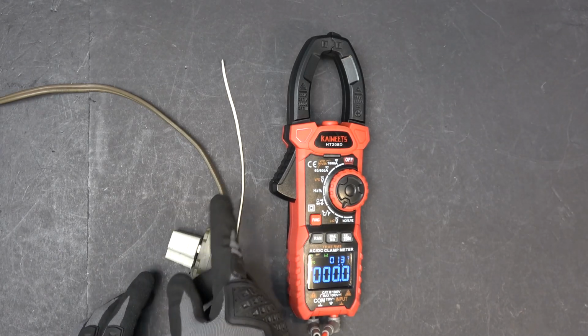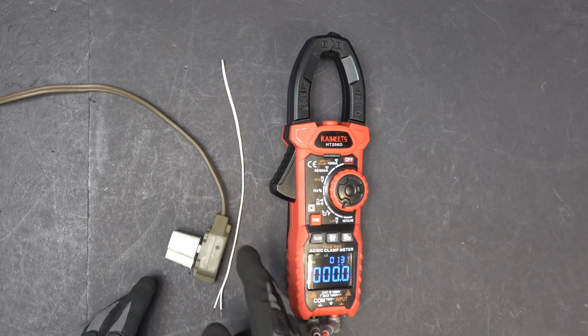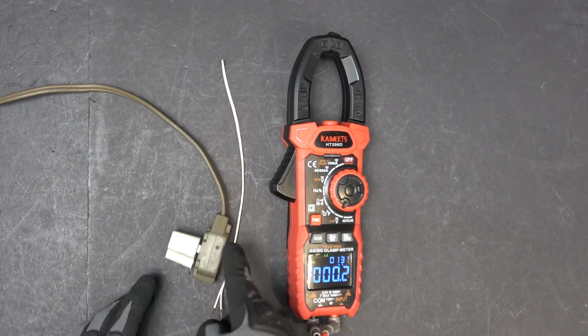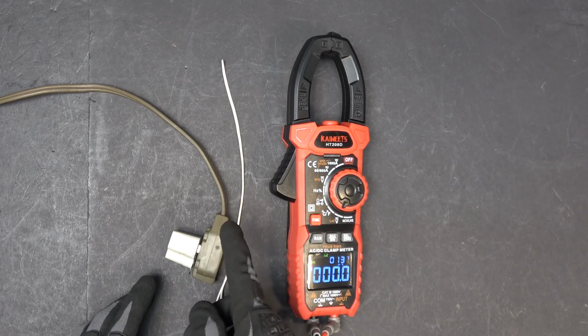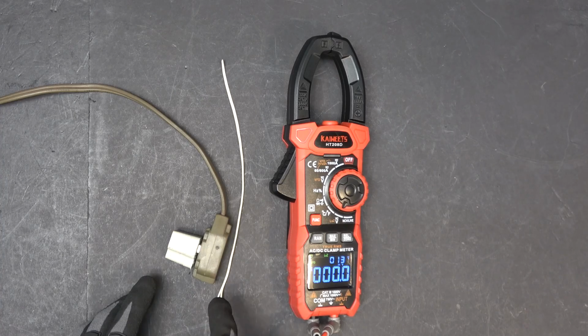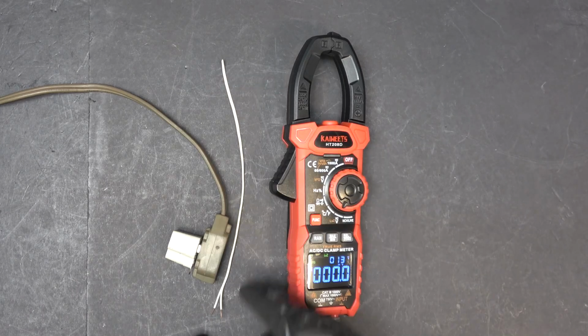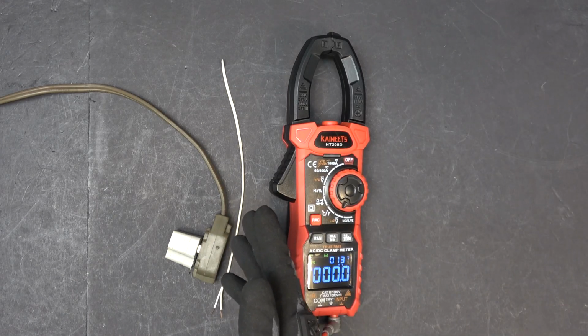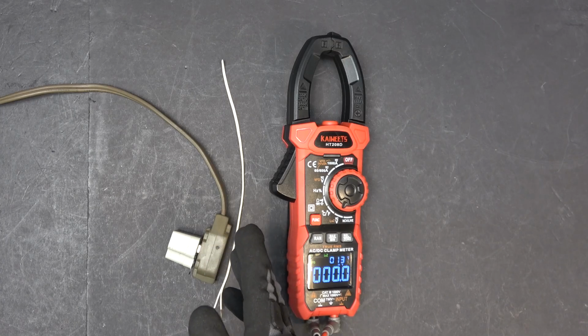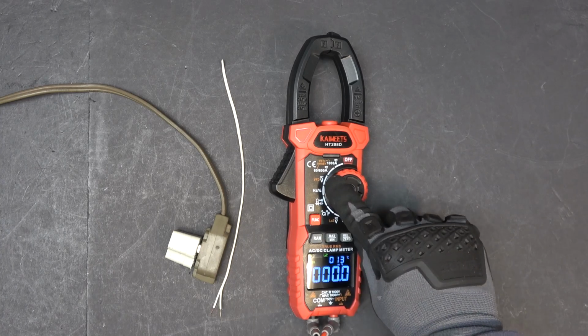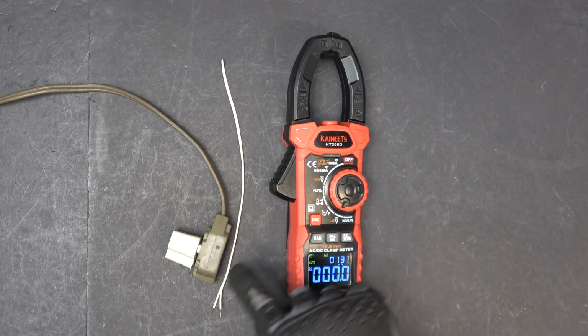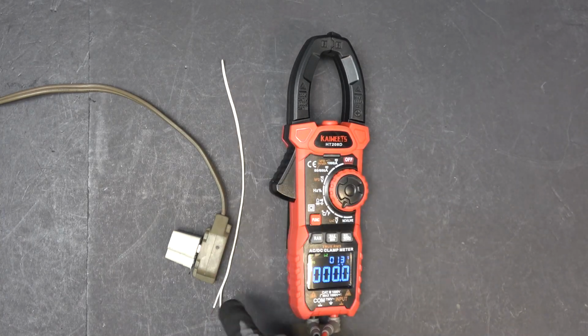And this wire, because it's live, it has a magnetic field through the wire, and because this bare wire is right next to it, it's influenced by the magnetic field and it produces a ghost voltage even though it's not connected to anything. This is the same effect in the transformer, except that this magnetic field here is not being amplified. So if I measure the voltage coming out of this white wire here, with regular voltage reading, it will show some voltages, even though it's not connected to anything.